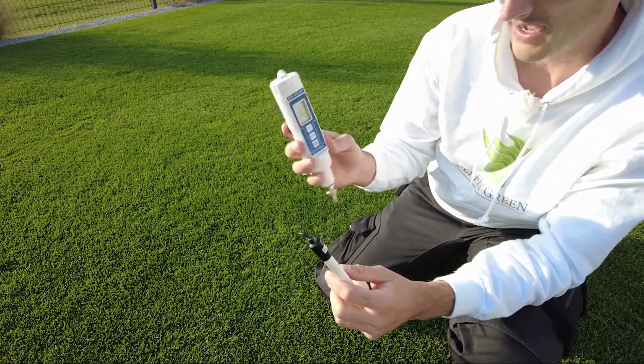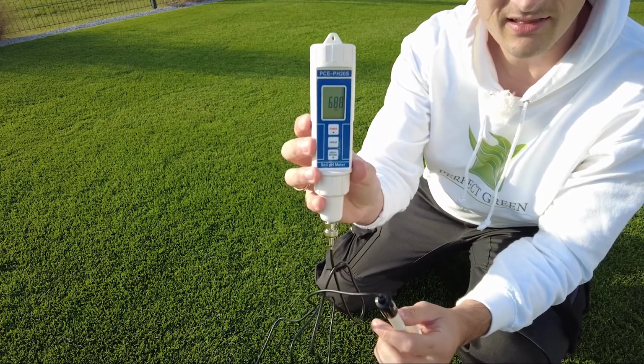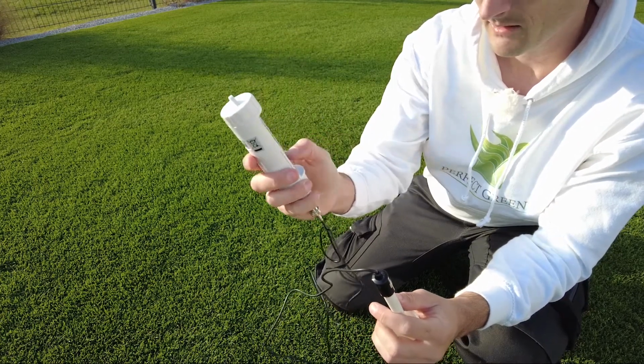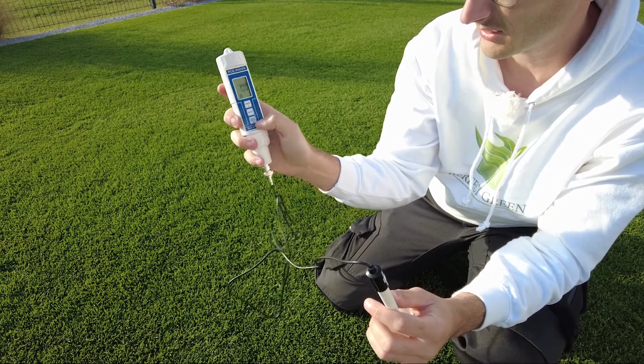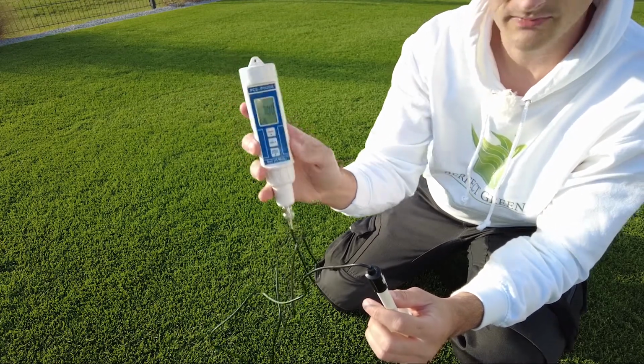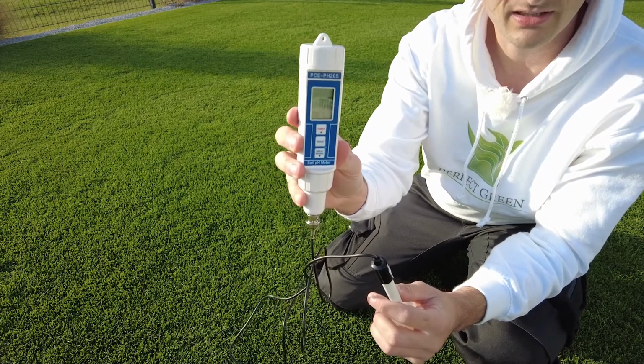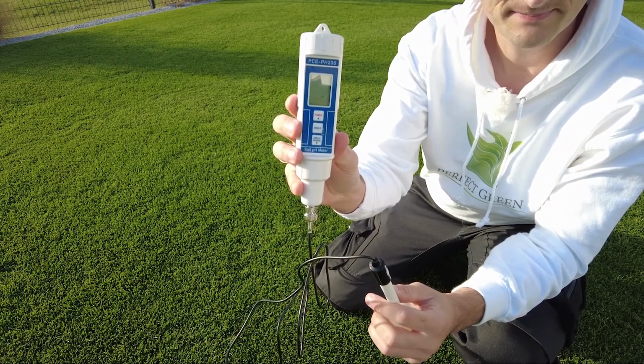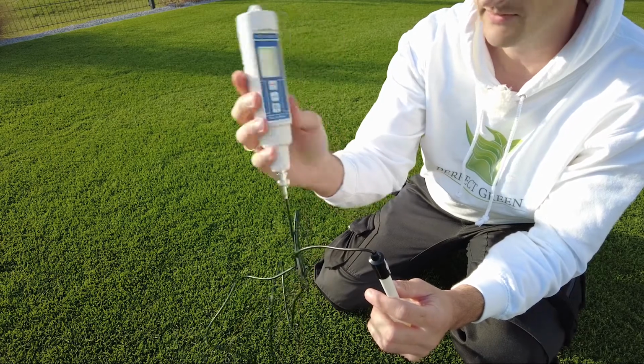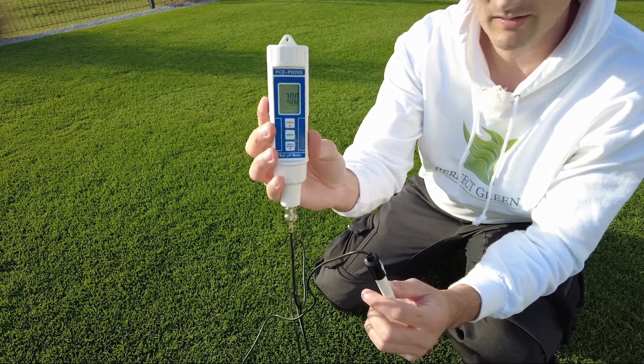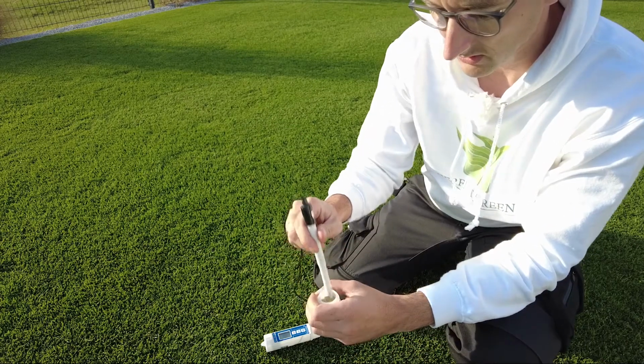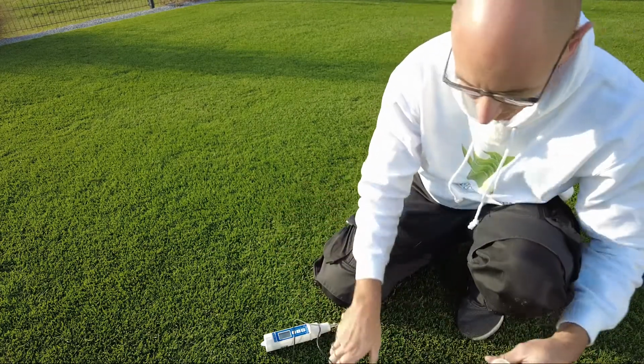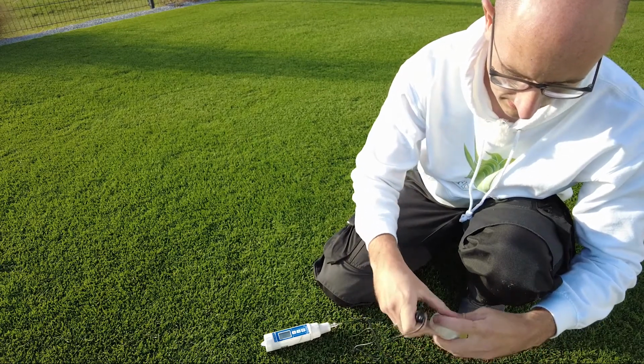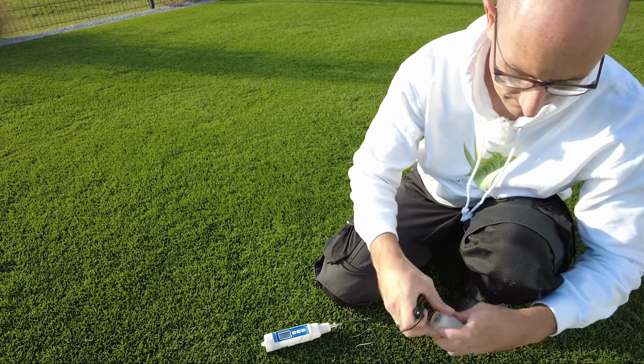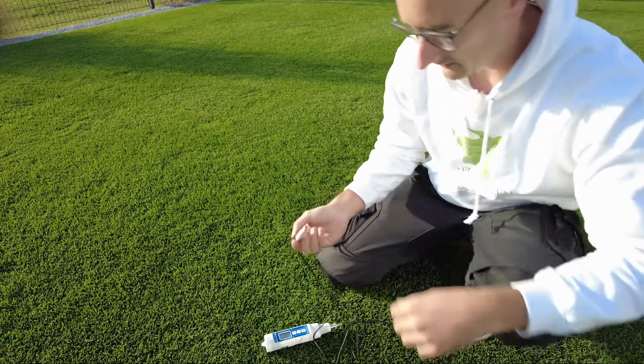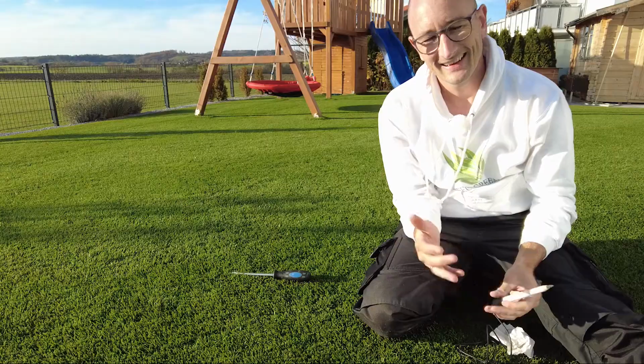It shows here 6.8, so it is not totally calibrated. I press once, hold, go down to 7 and press again, and then it will be calibrated. Good, that was it. Now it shows exactly 7.0. 0.07 is the tolerance of this device. Extremely exact. That was it. The device is calibrated. And now we can start.